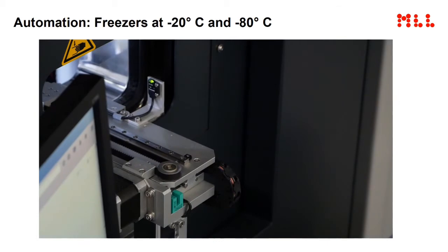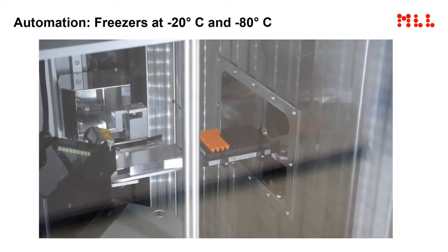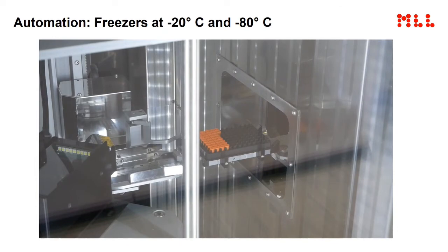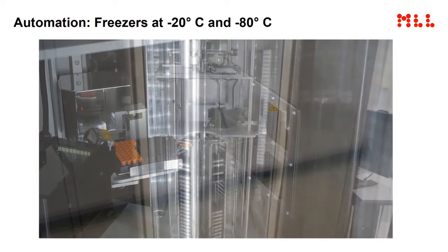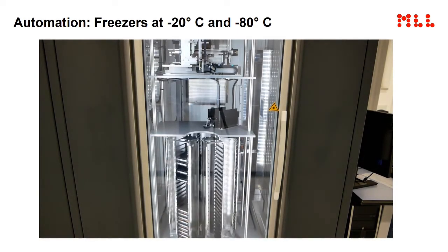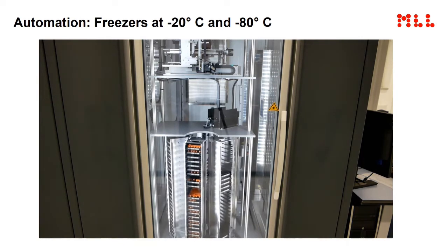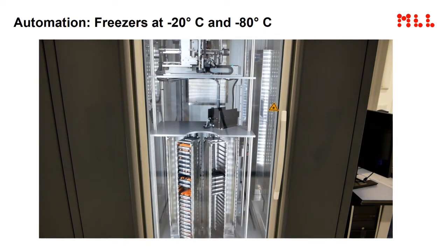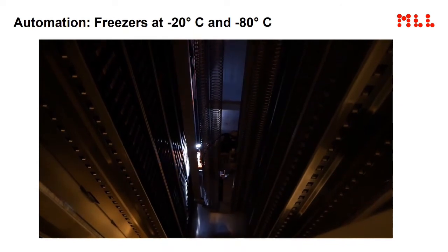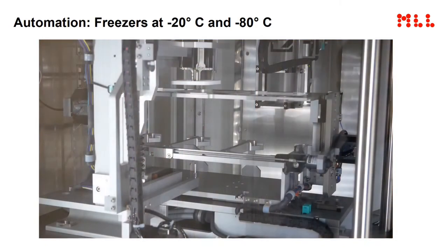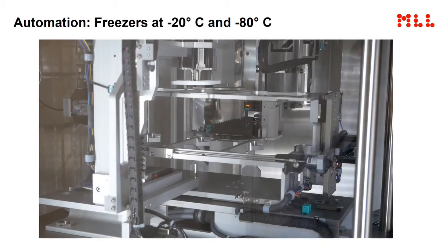And in a system of so-called chaotic order, the freezers completely automatically organize the respective samples to go in, or for the next morning to go back to another 96 well plate for DNA and RNA preparation, including also the primers for the respective assays that the freezer holds in addition and places to the respective plates before they go for DNA and RNA preparation. So these systems are completely organized in our workflow and combined with our LIMS system.